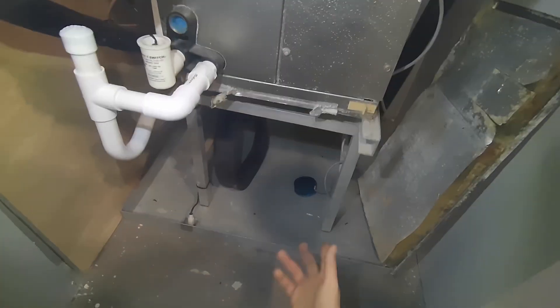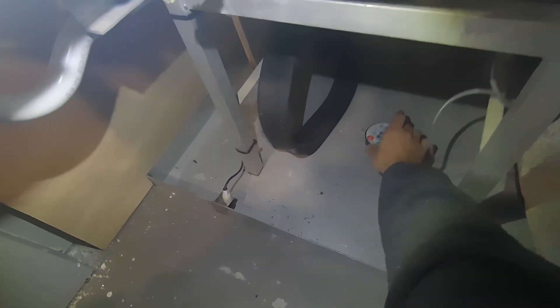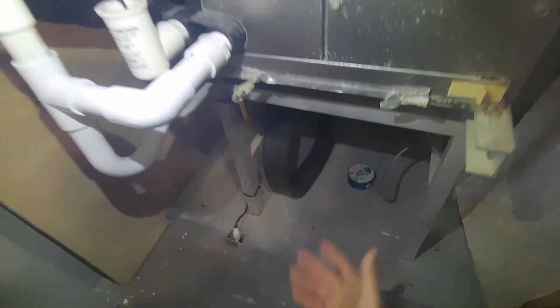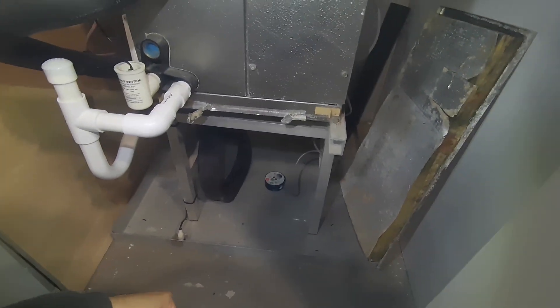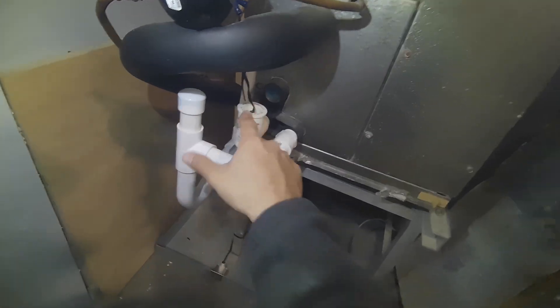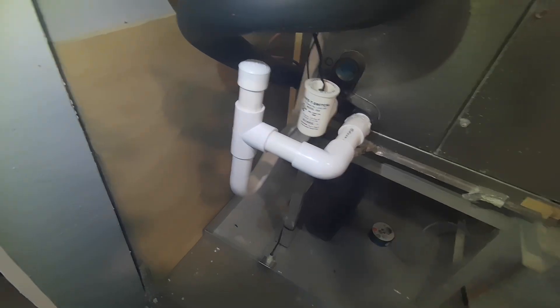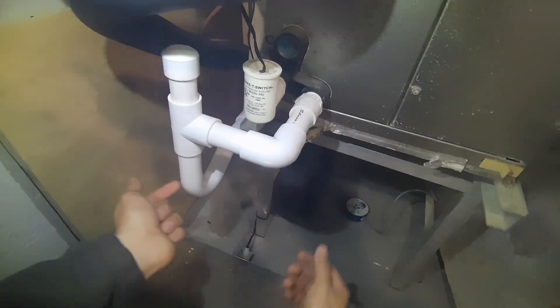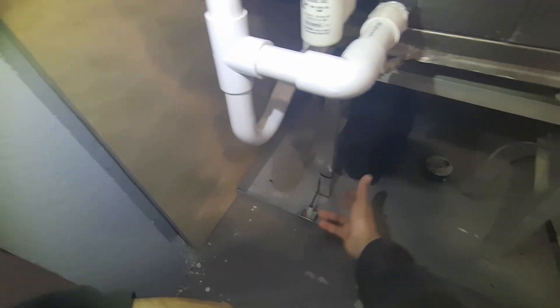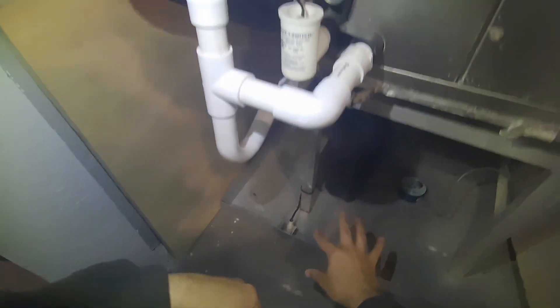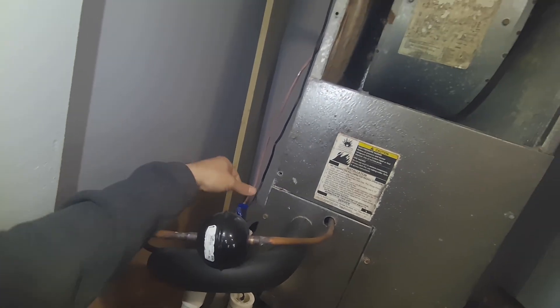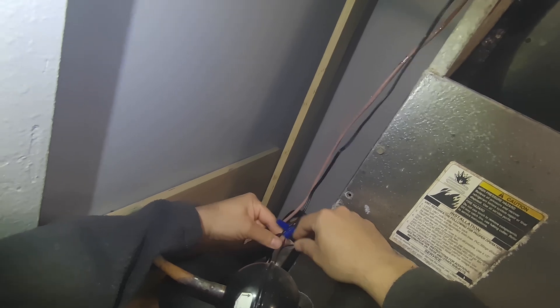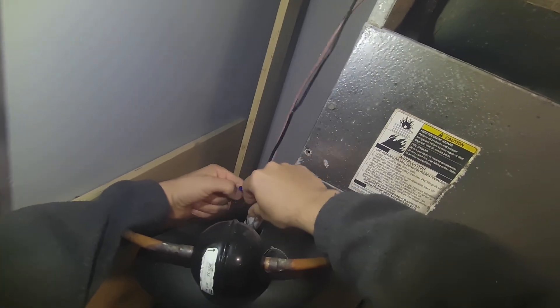As for this switch, I like to put it right in the center of the unit so as soon as it starts to drip it gets hit with it. You'll also notice there's already safety switches here, one in the pan and then one up here. Typically if you have one up here then you just need one in the pan, you don't need to add this one or vice versa. But this one's already here because I already have it in there and I did splice them together so they are in series.